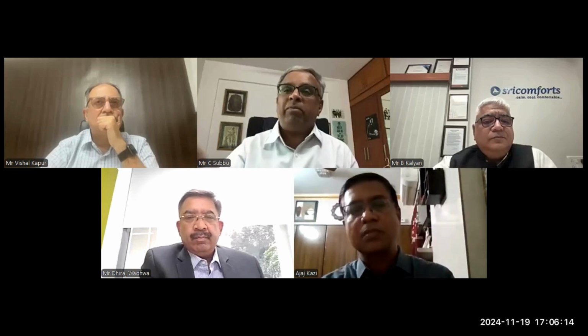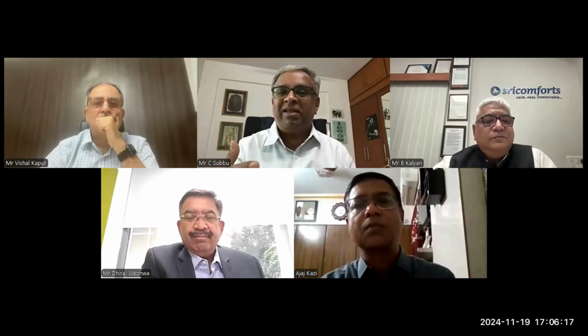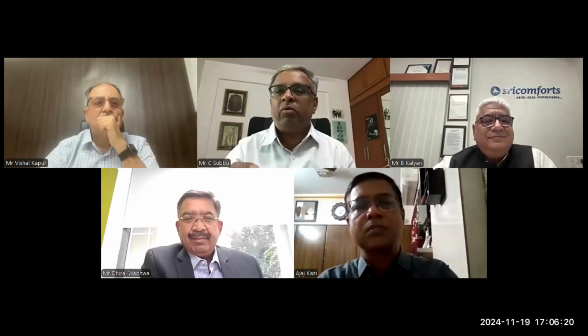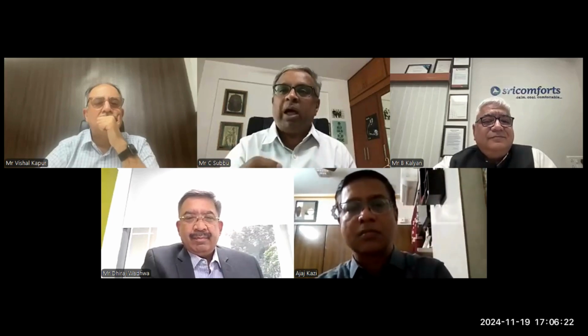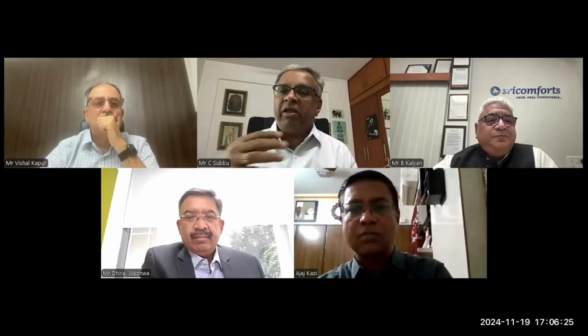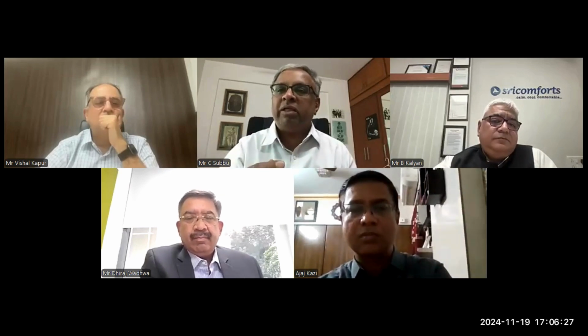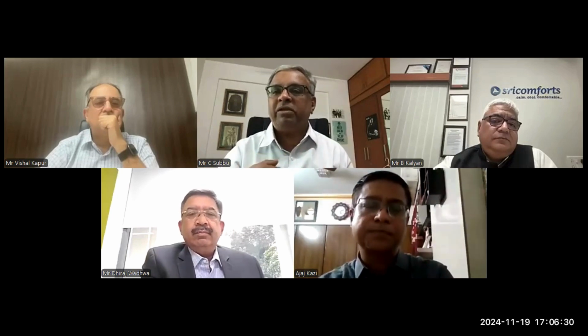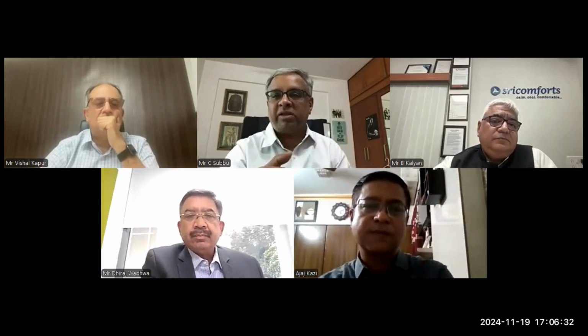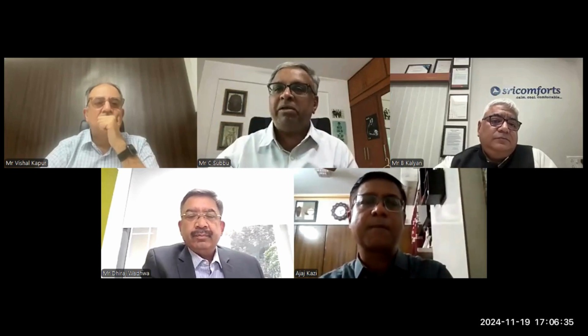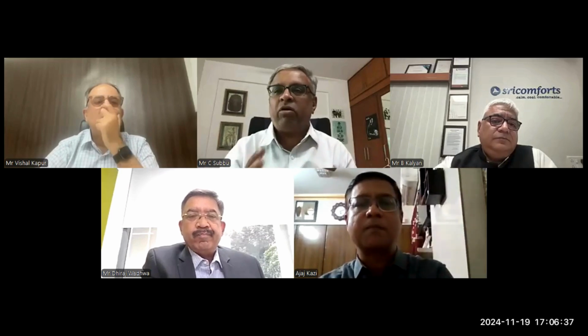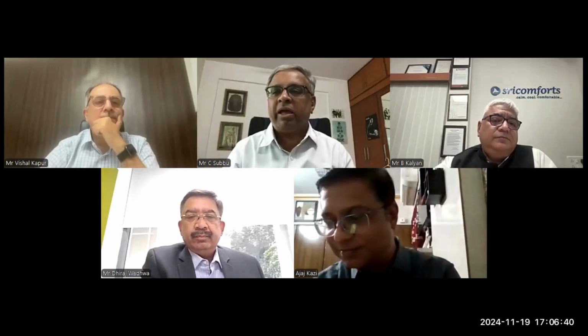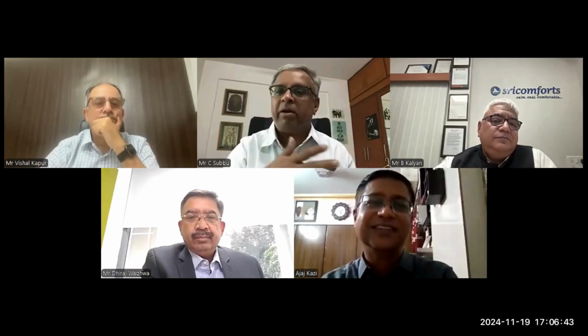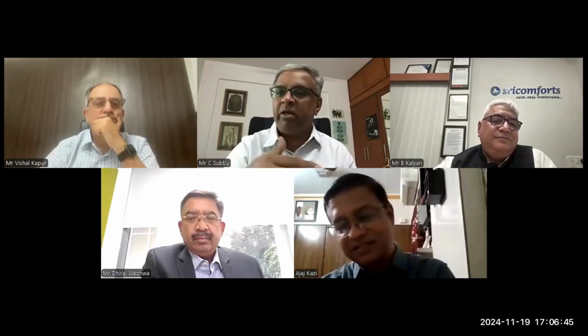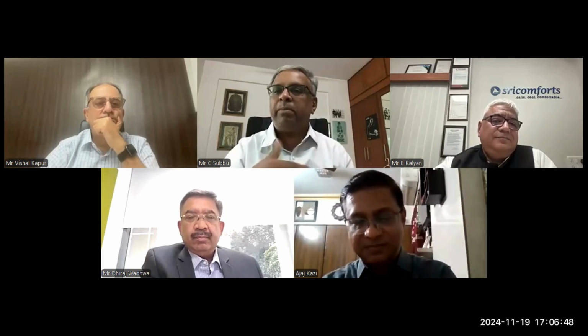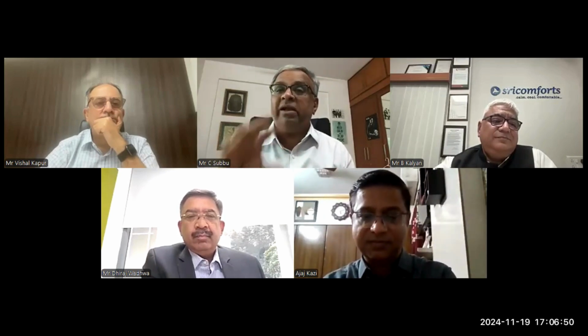But before we go there, we have to make the basic BMS system work. That is the one weak link that we have. Every contractor, every end user has to start getting their BMS capabilities up to speed. It should not be left only to a BMS contractor. It's not rocket science. Every HVAC contractor should get into testing, adjusting, commissioning, and BMS. They should build their capability, because only then will it be an integrated system.